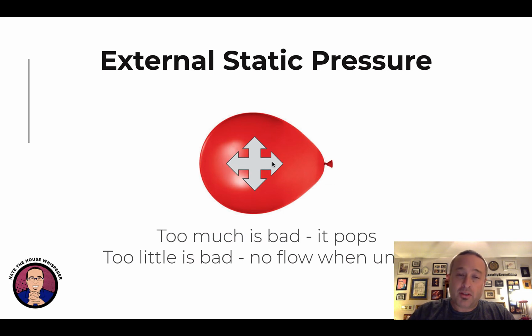But the problem is, if you have too much static pressure inside, the balloon pops. In HVAC terms, that puts a whole bunch of back pressure on the fan motor, and the fan motor will die very quickly, like in a year or two — and they're not cheap, at least $1,000 installed. But if you have too little static pressure, there's not enough pressure to flow the air. So there's a balance, not unlike blood pressure.